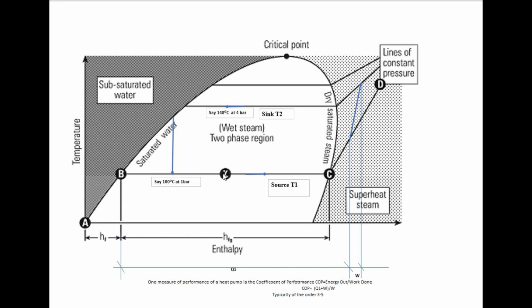So we keep adding heat, making it into steam. The quality of the steam improves until we get to complete dry steam. We then continue to add heat to it, so the temperature will now start to rise as well as the energy, and we'll keep going up on that constant line CD. But let's say when we get to this point here that we compress the steam using a Roots blower or some other centrifugal blower, and we arrive up here at say 4 bar after doing an amount of work W.